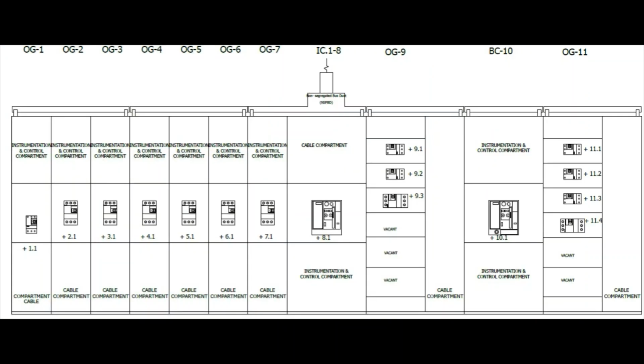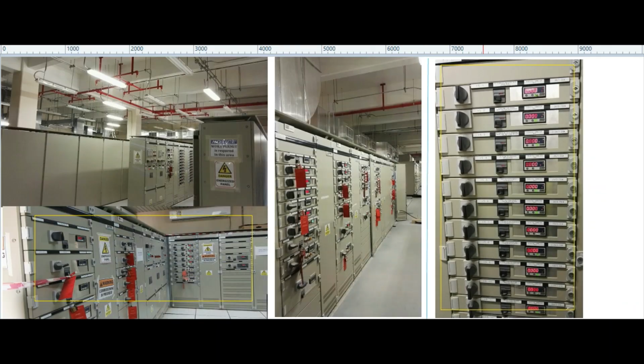So during commissioning stage, you can see as per the drawing also, in the middle of the panel lineup there is the incomer and others are outgoing modules. Suppose plus 9.1, 9.2, 9.3, these are the outgoing modules with some backend or spare feeders, motor or power feeders. This is the drawing for LV MCC.